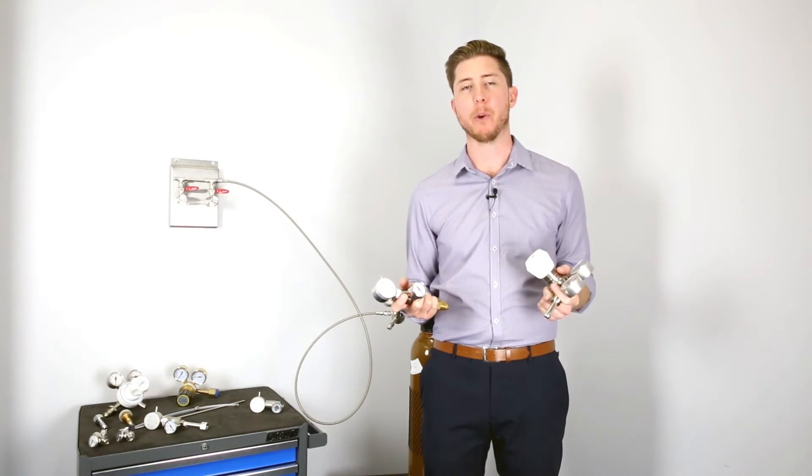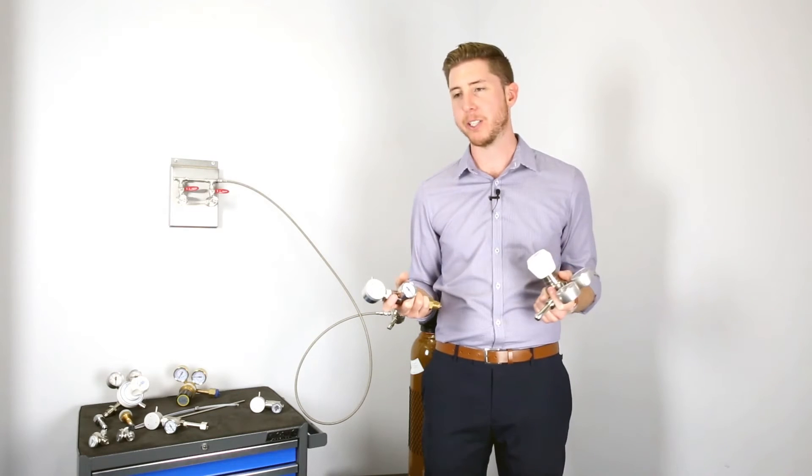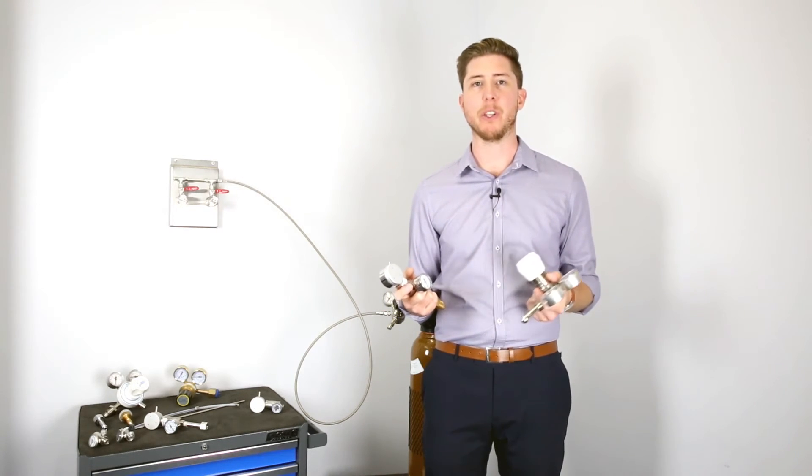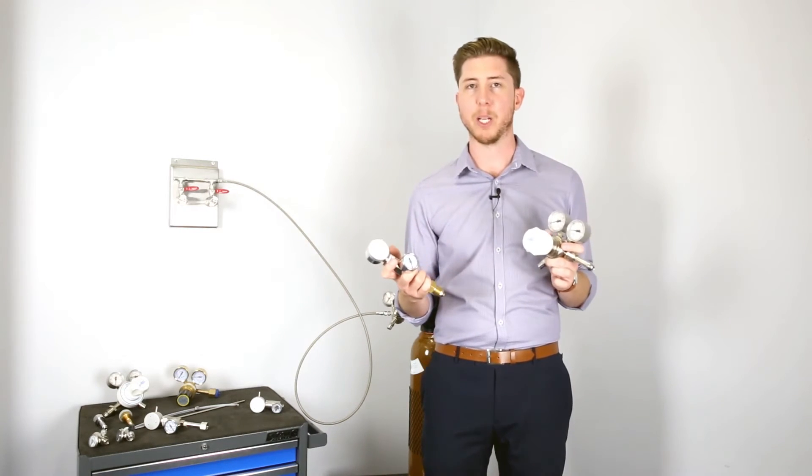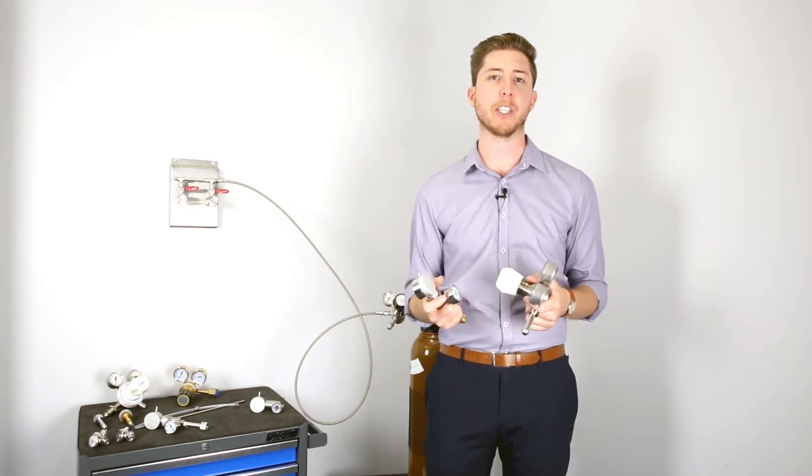The type of docking station will determine whether or not you need to use a pressure regulator or demand flow regulator. Any docking station with an internal pump will require a demand flow regulator. A docking station with an internal flow regulator or pressure system will require a pressure regulator. All regs are available in stainless steel, nickel-plated brass or brass based upon the corrosive nature of the gas mixture.